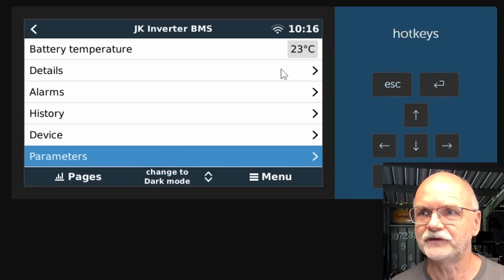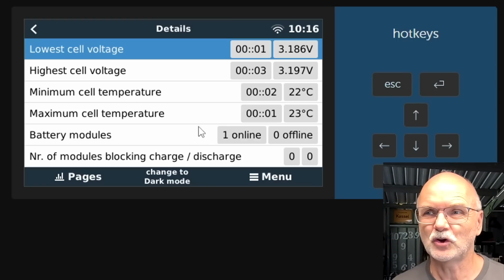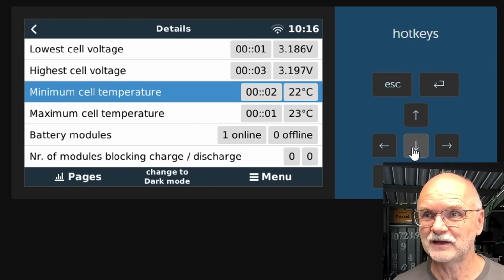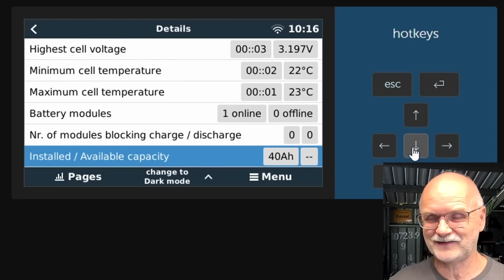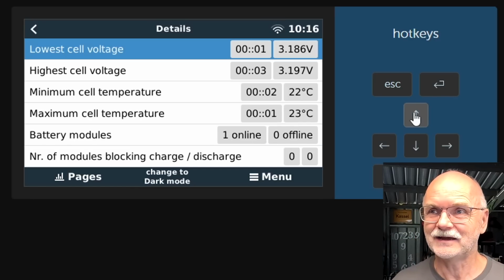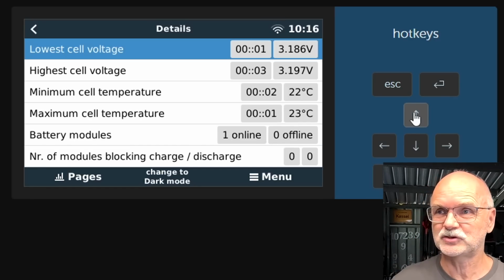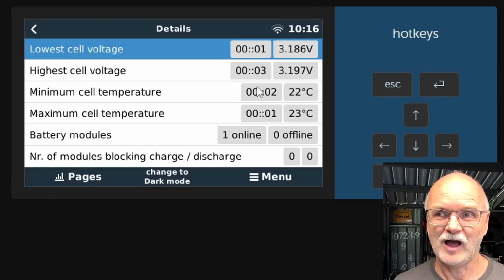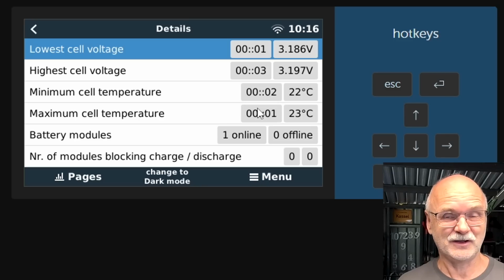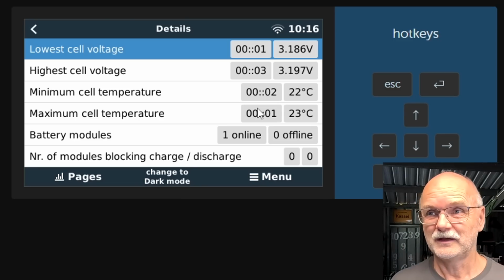Let's go back in here quickly and go to details. It will only show you one battery is online, obviously, with 40 ampere hours, which is not correctly set up now, but it doesn't matter. You can see the highest and lowest voltage and highest and lowest temperature here. This is all battery number 0, the master, communicating with your inverter. One module online.